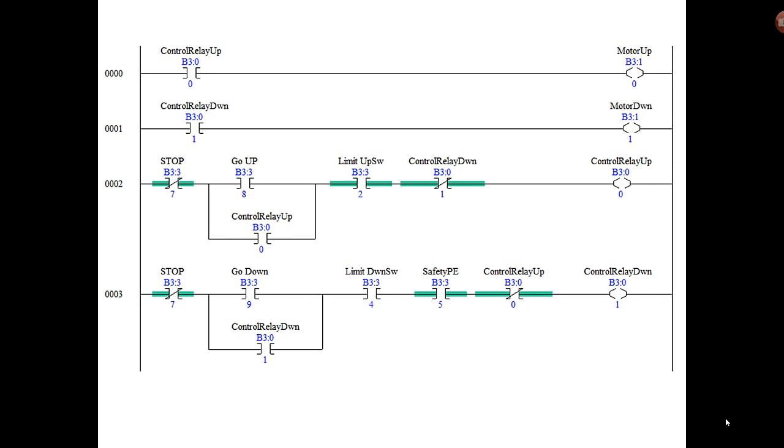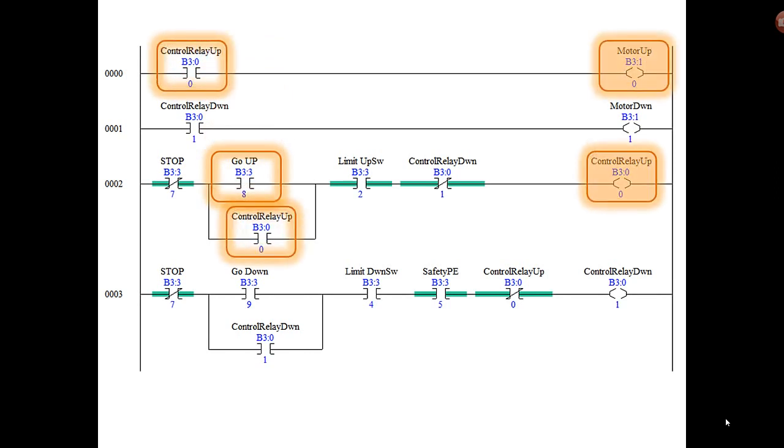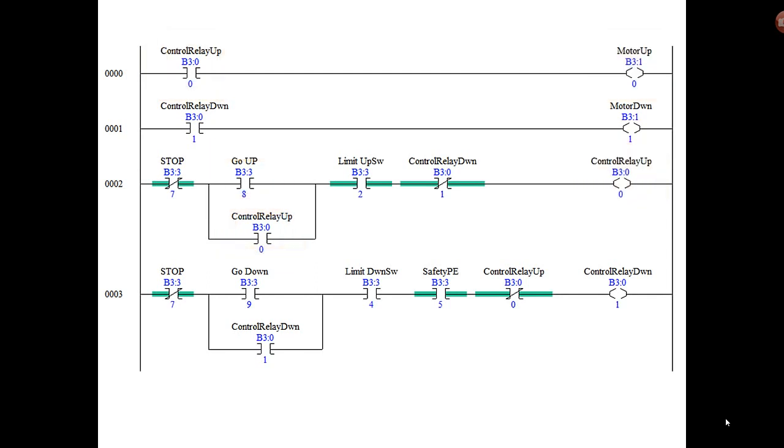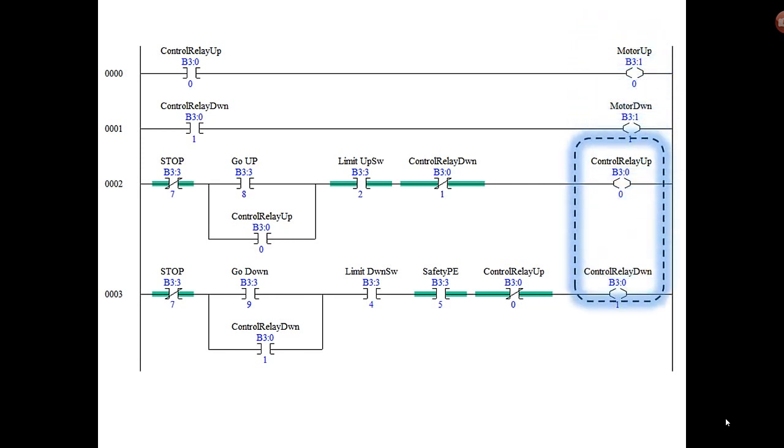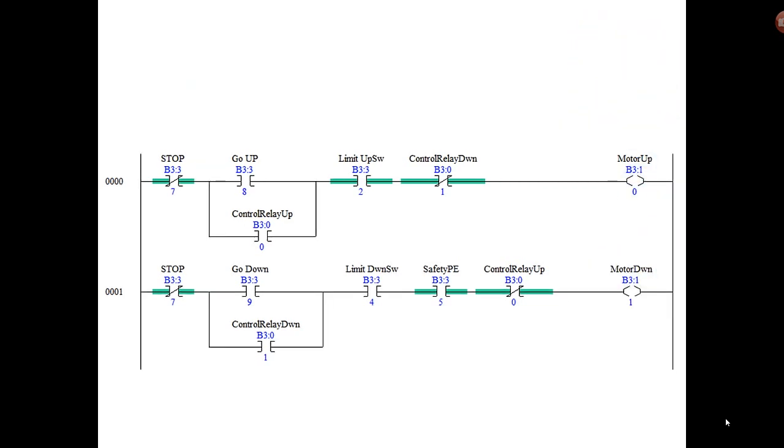Looking at this diagram, if we push the go up button it energizes the control relay up, which closes two contacts—one to bypass the go up button and the other to energize the motor up. Well, why have the control relay up that closes a contact that turns on the motor up? Why not just combine those? So we'll take these two and move them down to here and eliminate those two rungs of logic.